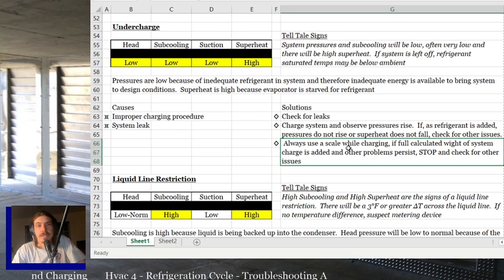That usually indicates an almost flat system. I mean, you might have a pound left in it, depending on obviously how much it holds. But typical residential system, you might have a half pound left in it. But if you ever have the system off, it's just sitting there for a little bit. It's 80 degrees outside, and you take the pressures, and your pressure is at 60 degrees saturation temp. Then your system's low on charge, okay?